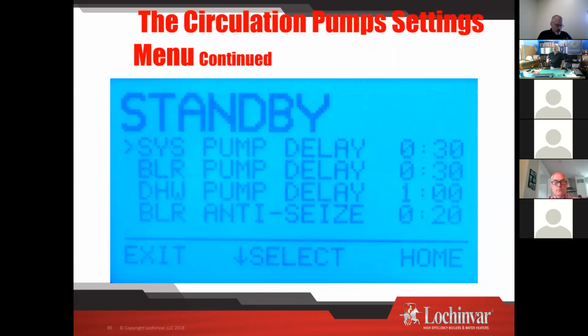Pump delay. How long does my pump run after its call to run is over? Whether it's a system pump delay, boiler pump delay, or domestic hot water pump delay. I would recommend adjusting your boiler pump delay and your domestic hot water pump delay. The higher your boiler temperature setting is for domestic hot water, maybe the longer you set that delay. So if you're running to 170 for domestic hot water and you're storing a tank at 130, you might give that a 2-minute delay. All it's going to do is continue to run and dump the rest of that energy out of the boiler and put it in your indirect tank where it belongs.